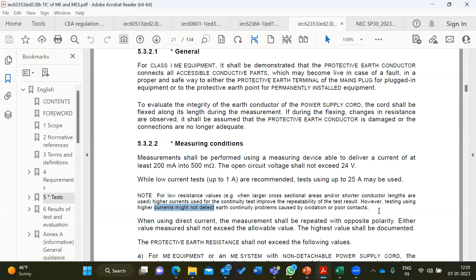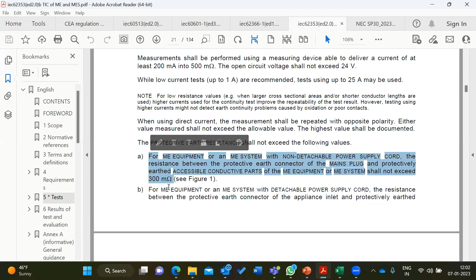This standard explains how to make a routine test of your biomedical equipment, and after repair, what kind of tests the biomedical engineer should carry out before putting this equipment into service. For example, here, for medical electrical equipment, I'm reading the clause: for medical electrical equipment or an ME system with a non-detachable power supply cord, the resistance between the protective earth connector in the mains plug and protectively earthed accessible conductive parts of the ME equipment or ME system shall not exceed 300 milliohm. So this is a requirement for one type of equipment.